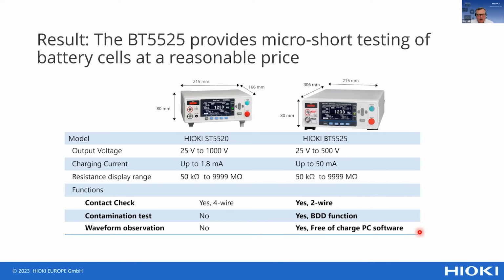And then there's another question: is this battery tester only useful for lithium-ion batteries, or can it be used for alternative battery technologies? Would you like to answer that one, or shall I answer that one? Please do so. Well, because it is a kind of a safety and insulation test, it doesn't matter what kind of technology of the battery you are using. So it is applicable for different types of batteries as well. If you're looking at solid state batteries, it might be a little bit different, but if you are working with a liquid, then it's not an issue. You can use this battery tester for all those applications.